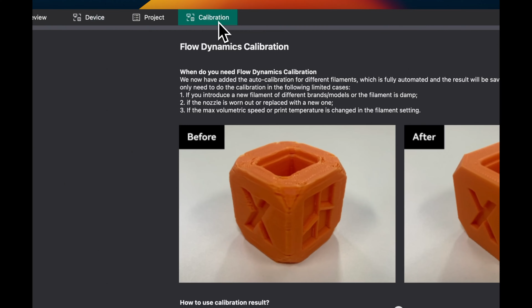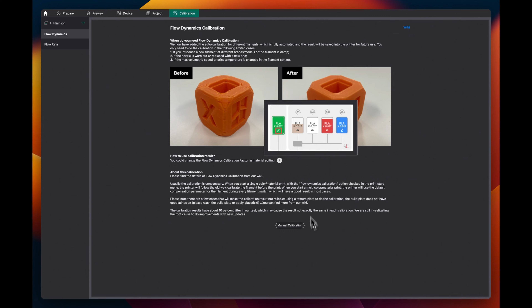But the calibration I'm certainly interested in is the filament one. Just a final word on the machine calibration: when you first get it, it's best to run that. Okay, so back to the filament calibration. We're going to run through it, and we do this to make sure that the filament comes out the absolute best it can, and we click manual calibration.